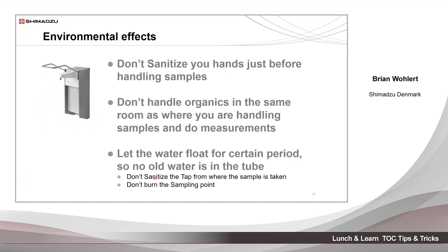Another thing is that at most or several customers, it's the microbiology laboratory who takes out the samples for the TOC analyzers. And one thing they do when they take samples, they sometimes sanitize the tap before taking the sample, or even burn the tap before they take the sample. Both of these things create carbon, and this will come into the sample and we will measure it right away.